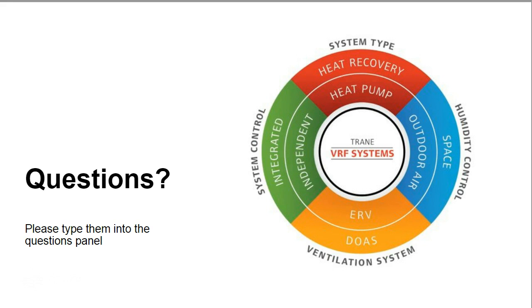Pipe sizes are already going to be in the system, but enter those lengths and the number of hard 90 elbows into your system. When talking to VRF system installers, I always recommend the use of long radius bends to reduce the amount of additional refrigerant in the system.